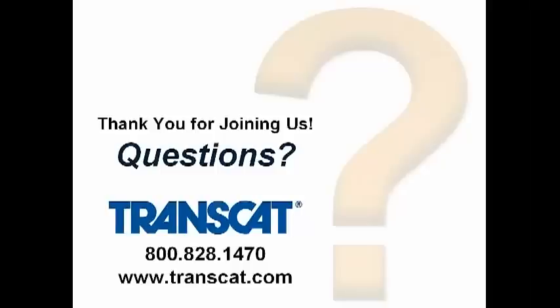And I think the question goes back to the wording around this subject. It comes down to a simple and/or in one of the statements, where you can interpret it one way to say you must provide uncertainties with every reading, versus as long as you're giving the tolerances to the client, then you don't have to report the uncertainty. So that's the debate, and we're waiting for a result of that. In the meantime, all of our calibrations are accredited regardless of service level.